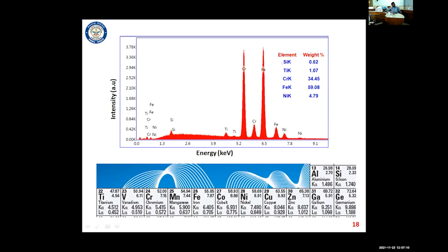Like that, you can see the silicon. The silicon energy is 1.74 kilo electron volts, which you can see here. So like that, based on the X-ray energy, you can identify what types of elements are present in your material. And also, how many X-rays are entering the counter will give the quantification of your particular element.